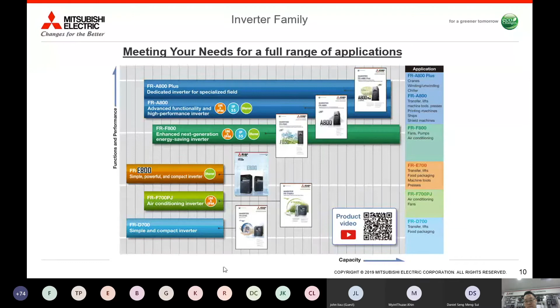So from the user's point of view, they may now understand that various types of inverters are to be used for various types of applications. If the users have already been using non-inverter systems to control their motors for quite some time, it usually takes some good reasons to convince them to look into inverters. So now we're sharing some of the key benefits of using inverters. First of all is energy savings, which is quite obvious, as I shared just now. The induction motor is not running at the optimum speed at all times of the day. At certain points of the day, you need lower loading conditions. That's why you can use an energy saving device such as an inverter to run the motor at the required speed at a point in time, which translates into energy saving.